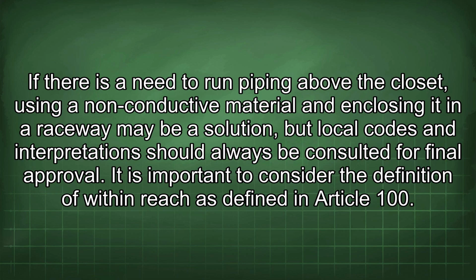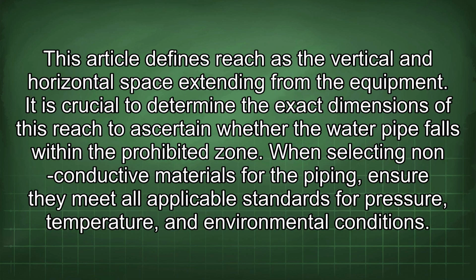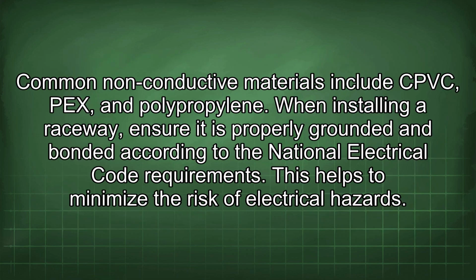It is important to consider the definition of "within reach" as defined in Article 100. This article defines reach as the vertical and horizontal space extending from the equipment. It is crucial to determine the exact dimensions of this reach to ascertain whether the water pipe falls within the prohibited zone. When selecting non-conductive materials for the piping, ensure that they meet all applicable standards for pressure, temperature, and environmental conditions. Common non-conductive materials include CPVC, PEX, and polypropylene.